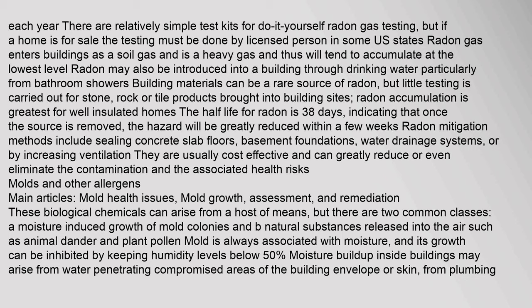Biological contaminants can arise from a host of means, but there are two common classes: moisture-induced growth of mold colonies, and natural substances released into the air such as animal dander and plant pollen. Mold is always associated with moisture, and its growth can be inhibited by keeping humidity levels below 50%.